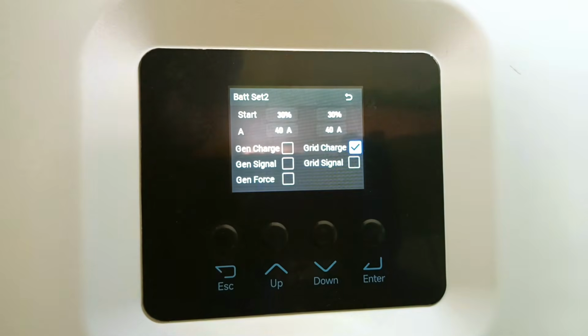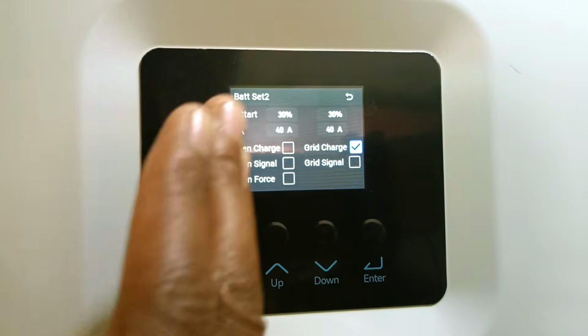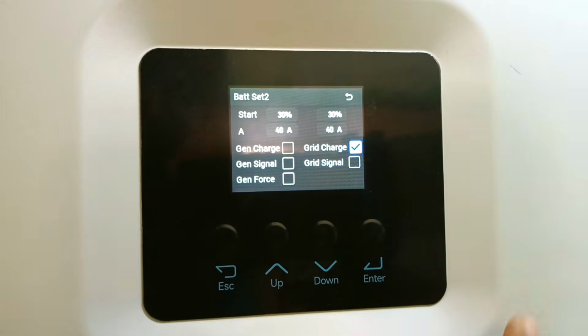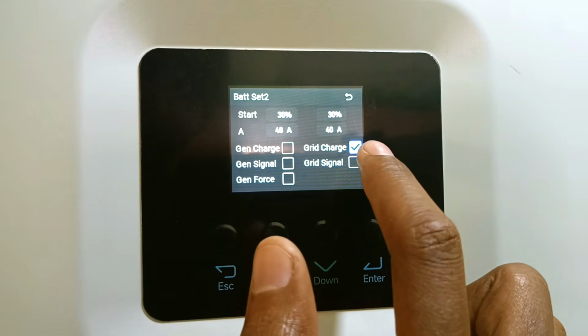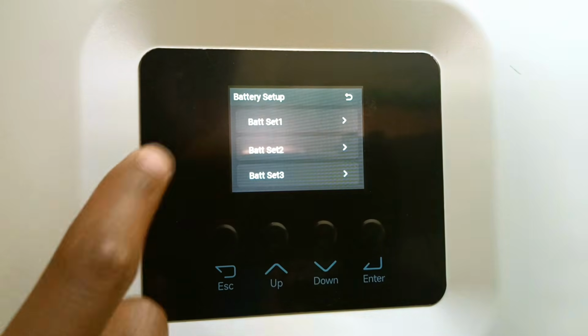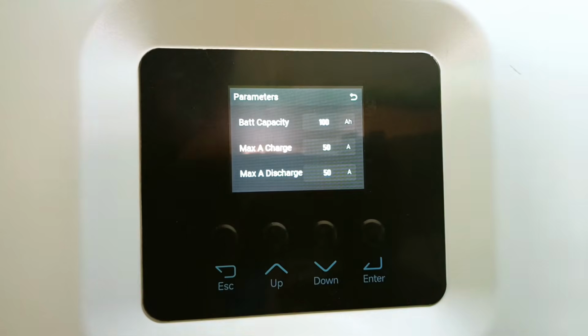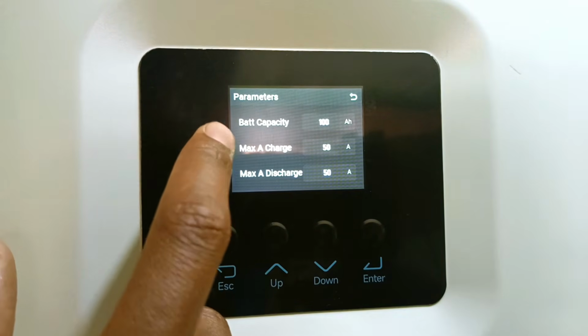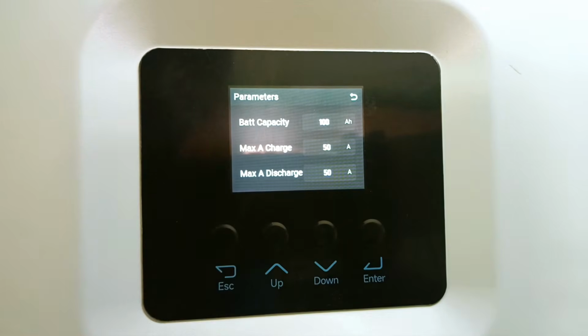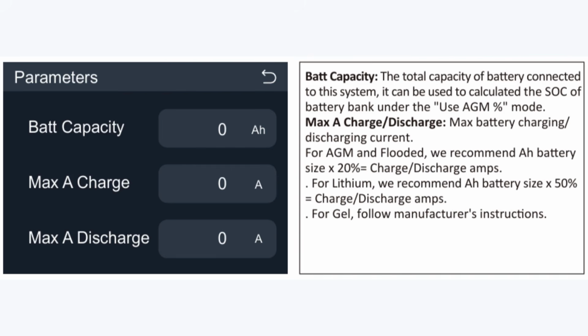Now let's get to battery set 2. On the left side is for the generator and on the right side is for the grid. This just says that this inverter is allowed to charge the battery via the grid. If we go back to battery set 1 and select parameters, you can see the battery capacity, maximum charging current, and maximum discharging current. I set this according to the user manual of the inverter, and let me read that to you. The total capacity of battery connected to this system, it can be used to calculate the SOC of battery bank under the use AGM percentage mode.